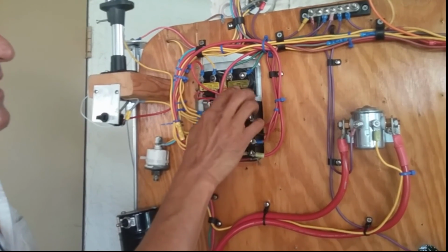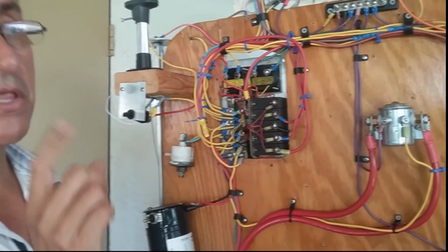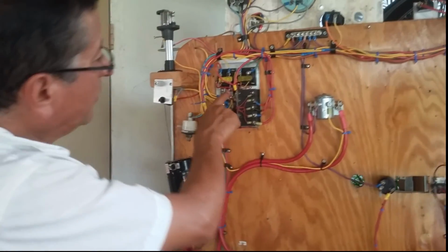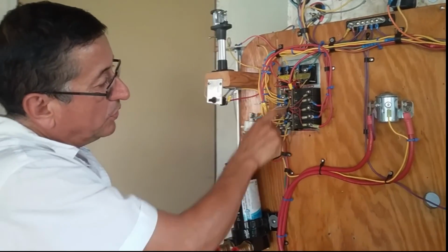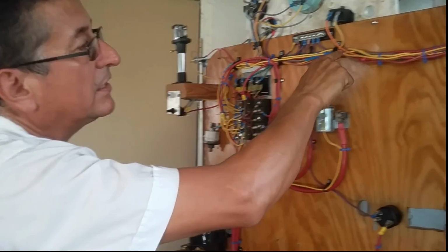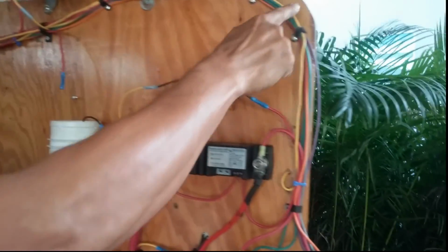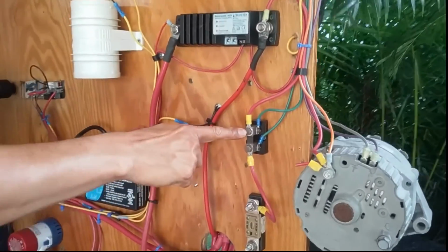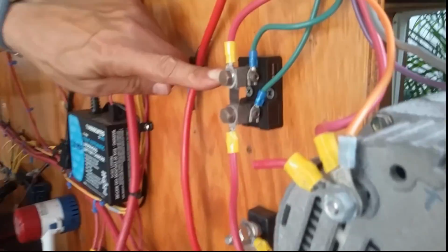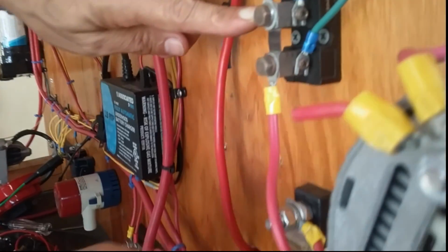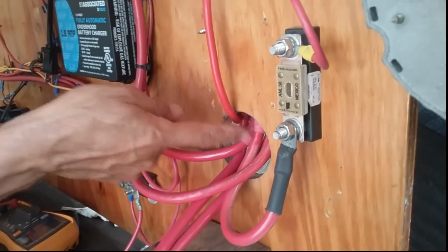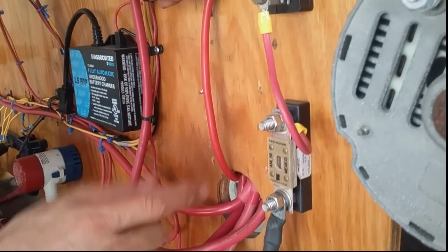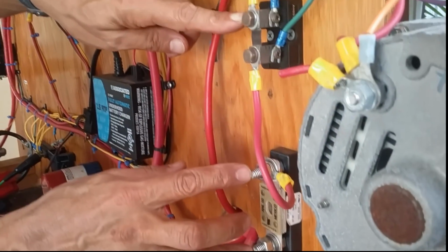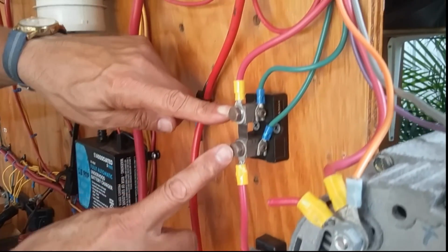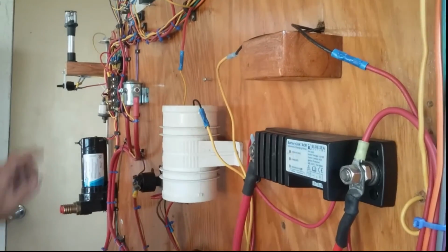Alright, let me explain how this ammeter is connected. You remember the positive cable to enter in the positive bus bar? That's the positive cable. Here, this is the shunt. And this is the other end. Enter into the fuse and goes into the switch selector. Okay, this is the power coming from the battery, passing through the fuse, and after the fuse, entering the shunt, and continuing, and goes into the positive bus bar of the panel.